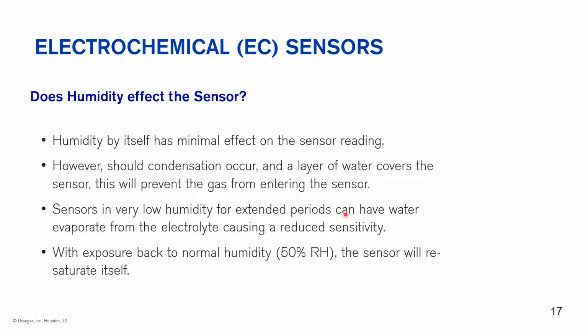Humidity. Humidity by itself isn't really that big a deal, except if it's a condensing humidity that could potentially condense over a sensor opening. In all my years of dealing with gas detection, I can't say I've ever seen that on a portable instrument, because the use and the motion of the units don't allow that to happen. There is a possibility in very dry atmospheres for extended periods that some of the water in the electrolyte can evaporate. That'll cause a reduced sensitivity. But if you get that sensor back into normal humidity, roughly 50% relative humidity, the sensor can actually resaturate itself and the sensitivity will come back.